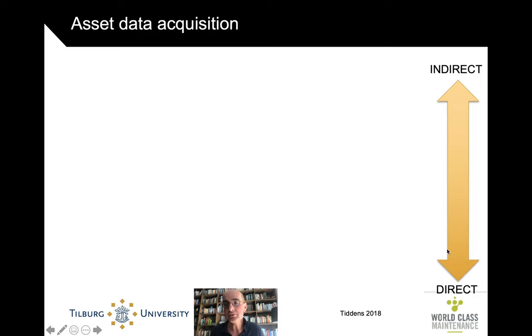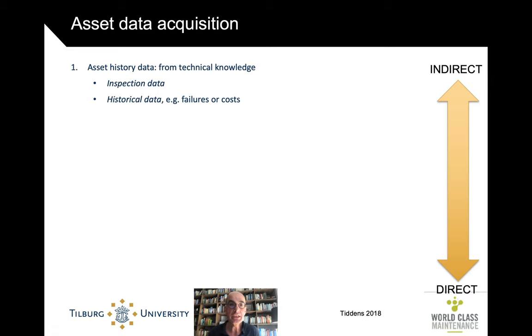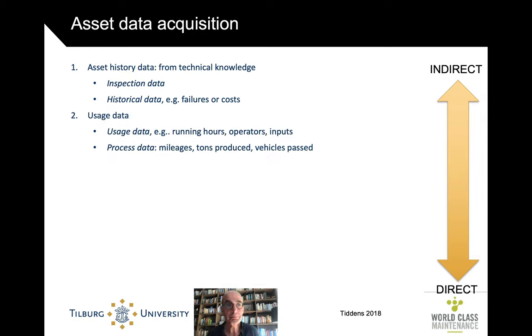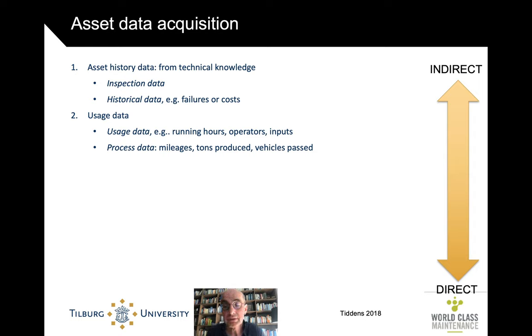Data acquisition can be more direct or indirect. Very indirect is taking historical data — inspection records of what has happened to this asset in the past. More direct is using the usage data: running hours, operators, input, but also things like mileage, tonnes produced, how many vehicles passed a road, or how far an aircraft or car drove. These are all indicators you can use for condition-based maintenance.